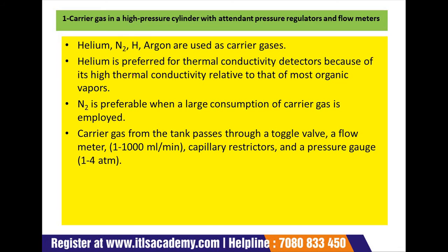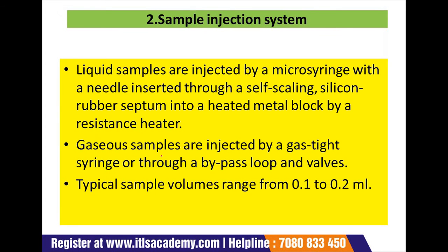The carrier gas used in this method includes helium, hydrogen, carbon dioxide, and argon. Helium is preferred for thermal conductivity detectors because of its high thermal conductivity relative to that of most organic vapors. N2 is preferable when a large consumption of carrier gas is employed. The carrier gas from the tank passes through a flow meter at 1 to 1000 ml per minute for capillary systems, with restrictors and a pressure gauge at 1 to 4 atmospheres.